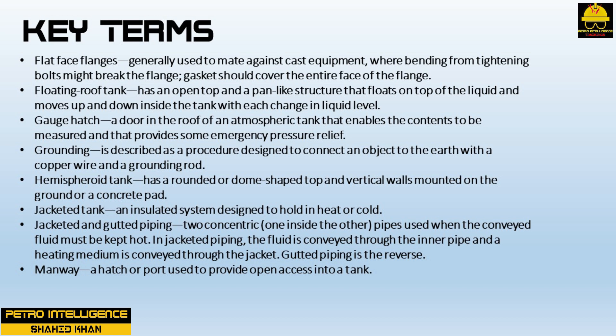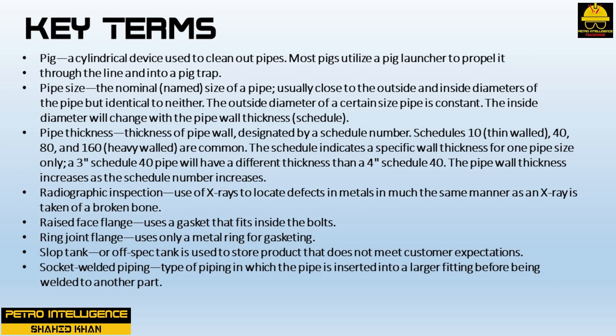A gauge hatch is a door in the roof of an atmospheric tank that enables the contents to be measured and provides some emergency pressure relief. Grounding is a procedure designed to connect an object to the earth with a copper wire and a grounding rod. A hemispheroid tank has a rounded or dome-shaped top and vertical walls mounted on the ground or a concrete pad. A jacketed tank is an insulated system designed to hold in heat or cold. Jacketed and gutted piping are two concentric pipes — one inside the other — used when the conveyed fluid must be kept hot. In jacketed piping the fluid is conveyed through the inner pipe and a heating medium through the jacket; gutted piping is the reverse. A manway is a hatch or port used to provide open access into a tank.